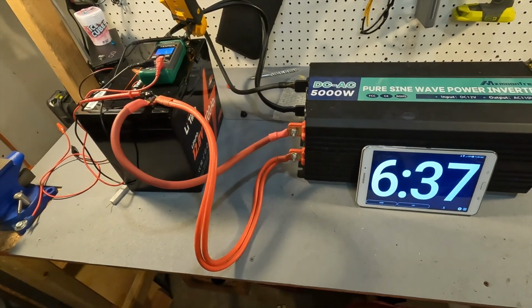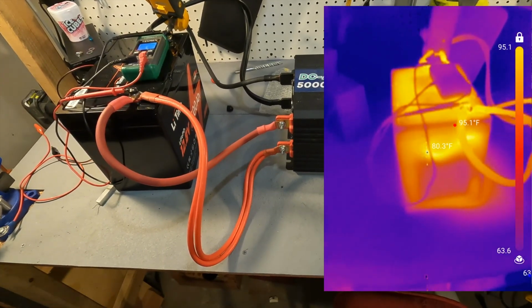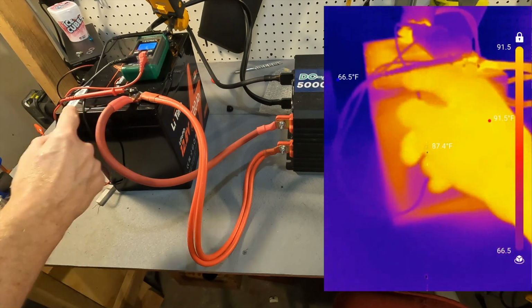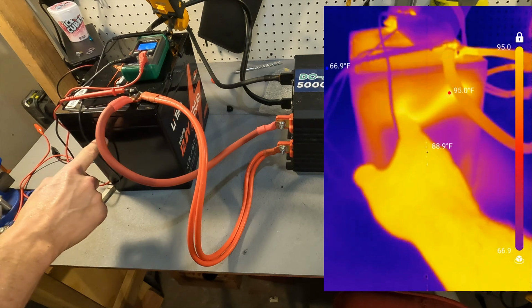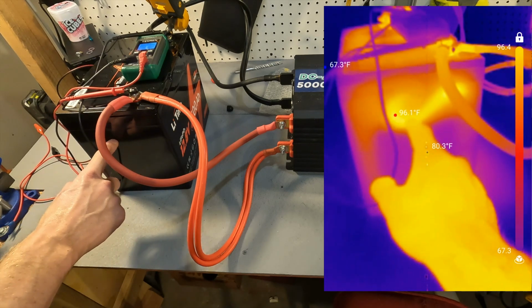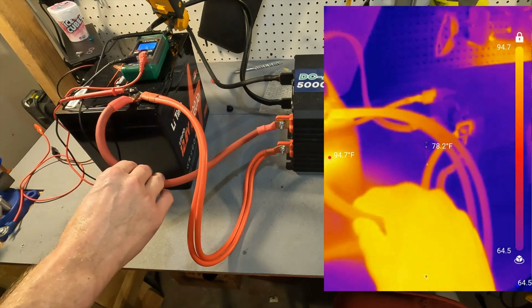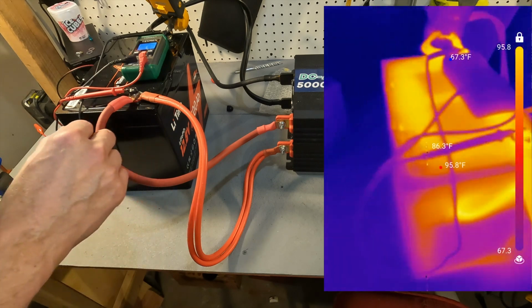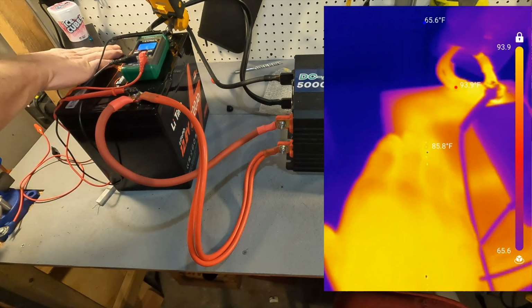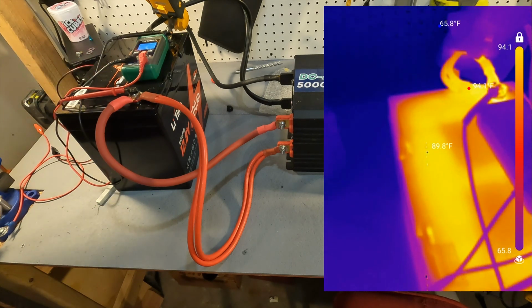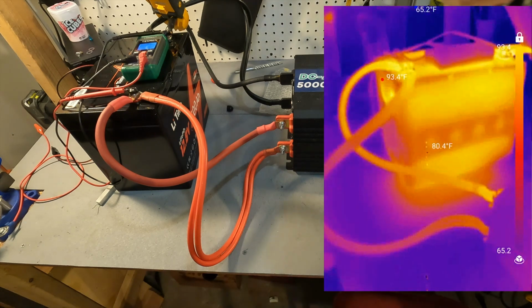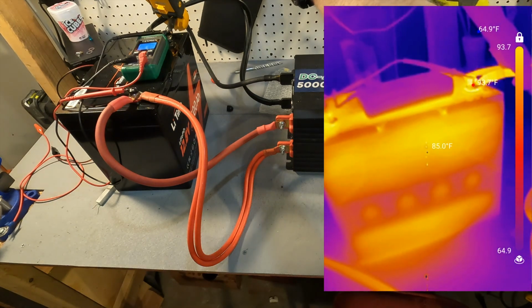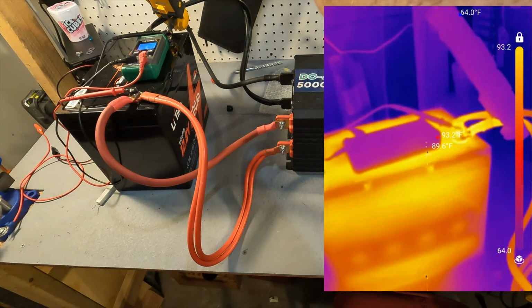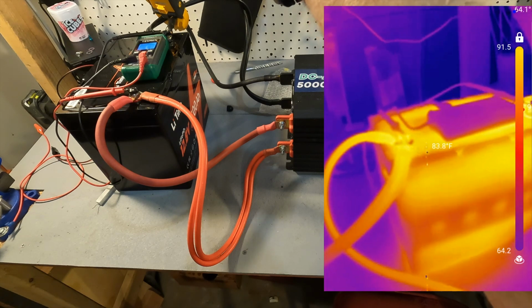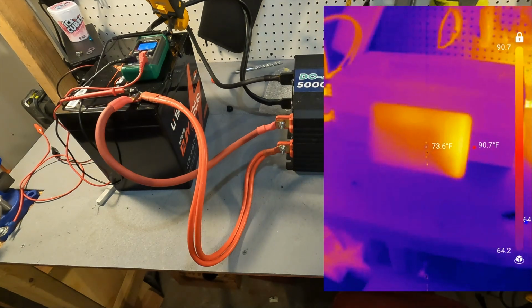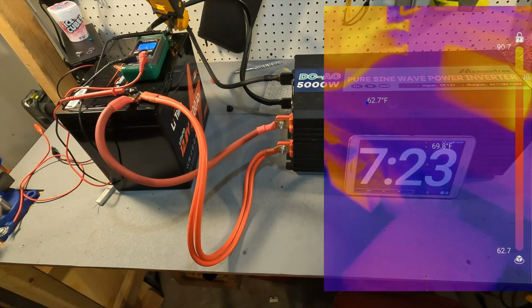So let's go ahead and look at the temperature of the battery. Let's scoot this back. All right, here is the temperature of the battery right here, and you can see on the front where a wire is, it's 95, 96 degrees, so it's actually warmer than the external batteries. On top, we're only looking at 85 degrees, so it's no big deal. And from the side, again, the case is only 85 degrees. Everything looks well within temperature for pulling 110 amps for over 7 minutes now.